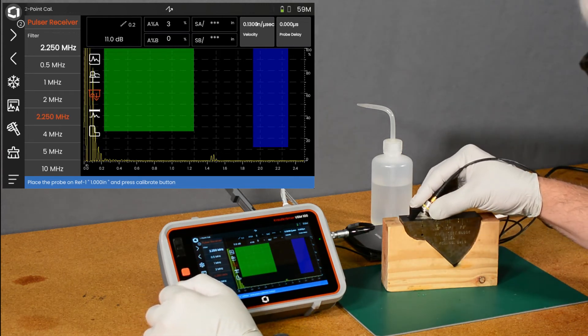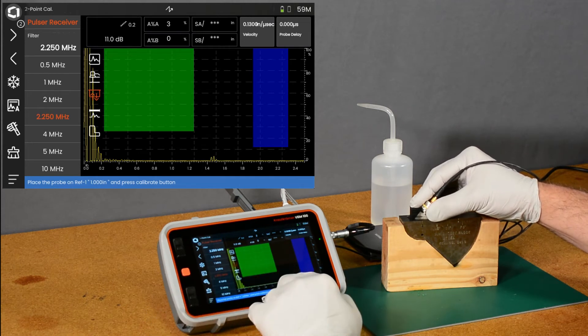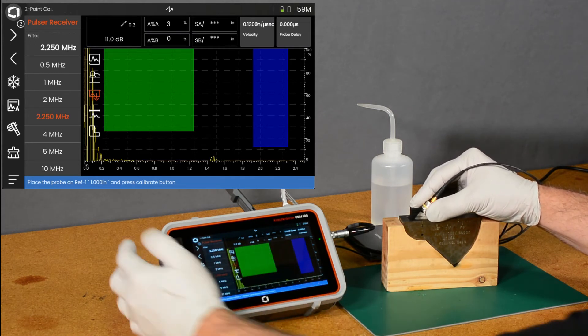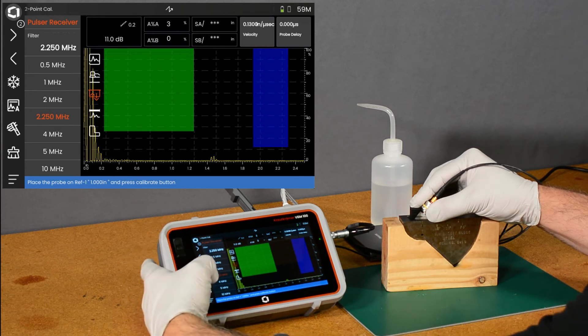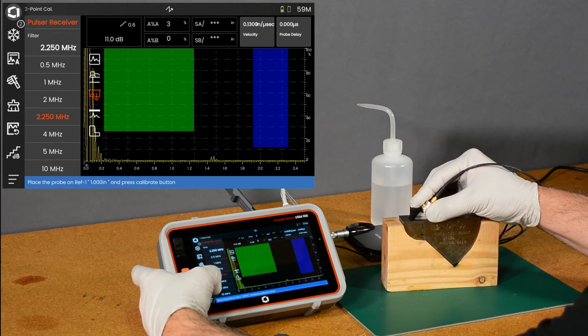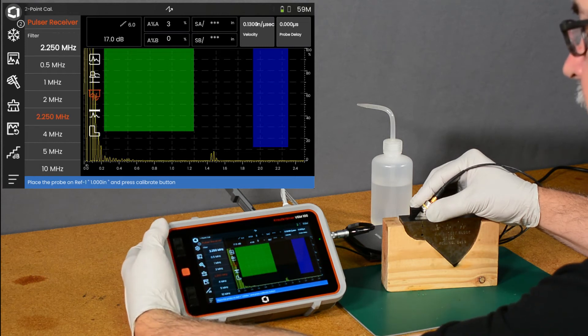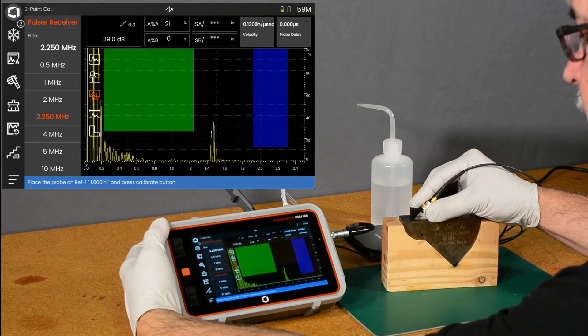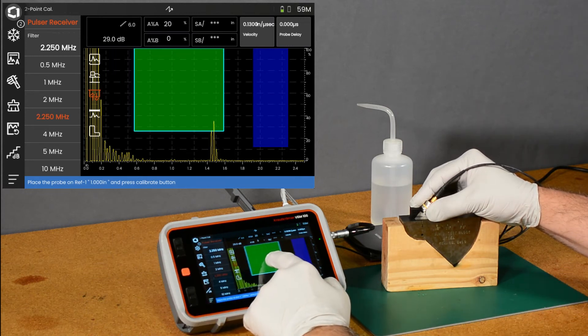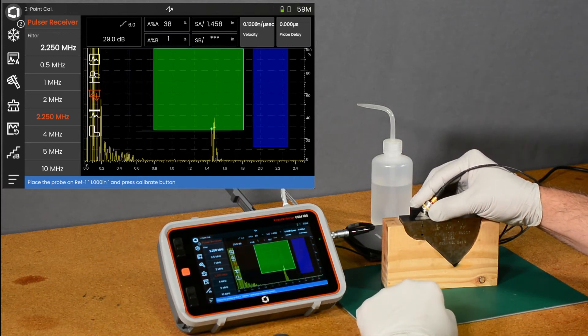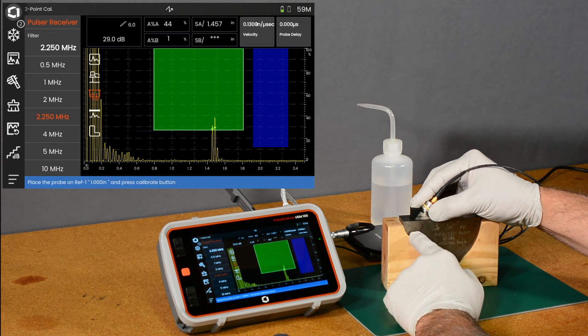And we start to see now our echo from the... Let's take our gain up. Let's change our dB step to some coarser steps. 6 dB steps for now. Give the gain a tap on the back.